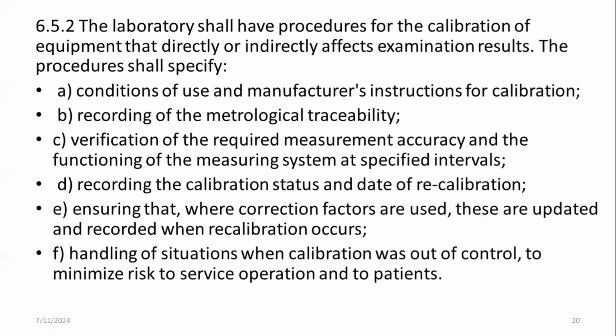And continuing on 6.5.2, it also tells us how the laboratory shall be able to perform the calibration of equipment that directly or indirectly affects examination results. And this procedure shall be able to specify the conditions and use of this equipment as per the manufacturer's instruction for calibration, recording of the metrological traceability, verification of the required measurement accuracy and functioning of measuring systems at specified intervals, recording the calibration status and date of recalibration, ensuring that where correction factors are used, these are updated and recorded when recalibration occurs, handling of situations when calibration was out of control to minimize risk to service, operations, and patients. So you see that even in the standard, calibration is talked about.